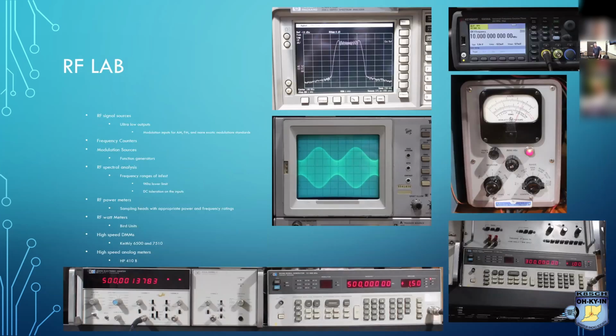An RF lab, where it gets fun, is RF signal sources, very similar to the HP over there. One of the good things about RF signal sources is the low output. A function generator usually can't get low enough, even if the frequency range is useful. To tune an AM or FM receiver, you have to put 7 microvolts on the lead that wraps around the antenna. There's not a lot of gear that does that, it's special made. The RF signal source only outputs at the high end 2 volts, so it won't scream in anything, but it's also safe to put right in the front end of a receiver to align and calibrate it.